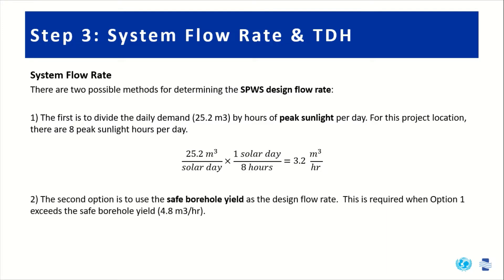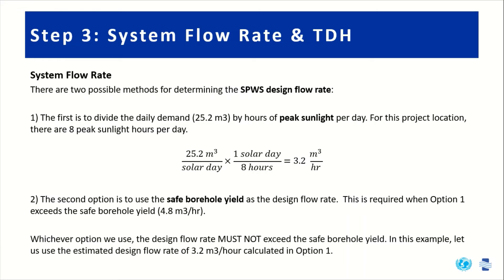The second option is to use the safe borehole yield as the design flow rate. This is required when option one exceeds the safe borehole yield. For this project, the safe borehole yield was 4.8 cubic meters per hour, and our result from option one does not exceed that. Whichever option we use, the design flow rate must not exceed the safe borehole yield. In this example, we'll use 3.2 cubic meters per hour from option one.